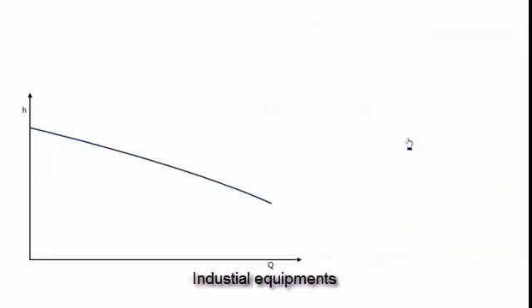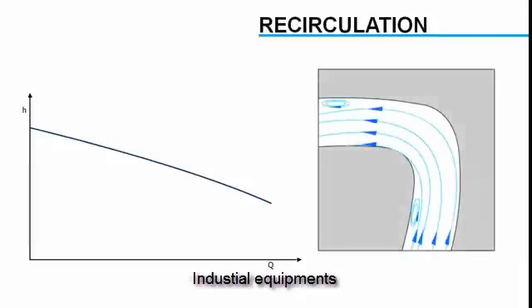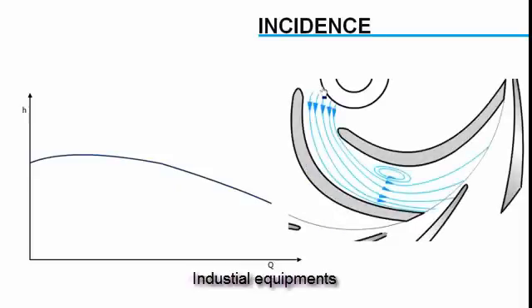Next is due to recirculation effect in the flow. When flow is below the design flow rate, recirculation losses become predominant, as shown in figure. When pump operates at its design flow rate, recirculation loss is almost zero. If there is a difference in blade angle and flow angle, it will cause further loss. Here energy loss happens due to flow impingement and recirculation effect. This is again prominent in off-design flow conditions. So it tends to have higher losses as we move away from design flow rate point.